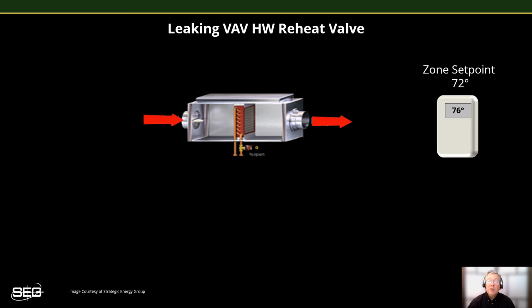And here we have another example of simultaneous heating and cooling that often happens. In this example, hot calls are necessitating bringing on mechanical cooling earlier than it should normally be needed. This slide shows a leaky hot water reheat valve out at a terminal box serving a zone out in the building, where the occupants frequently complain of it being too warm and stuffy and often request the cooling system be brought on early. By checking the zone temperature via the BAS system, we can see that the space is reading 76 degrees, which is 4 degrees over set point, so it's no surprise that they're complaining.